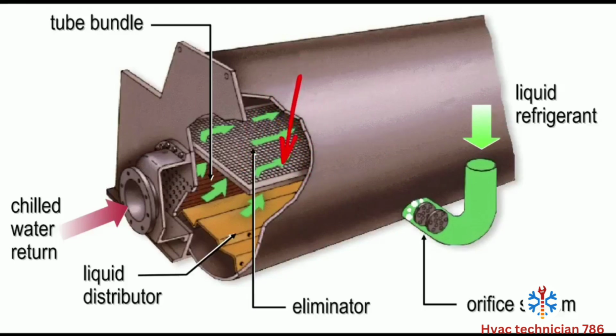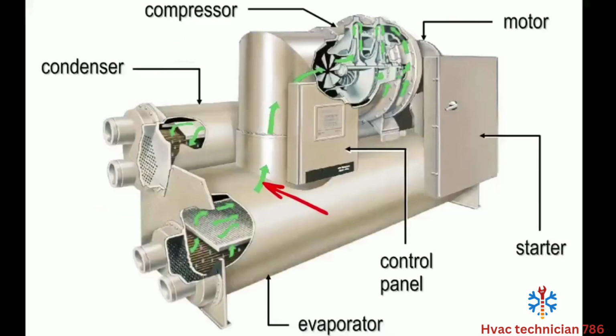So there is this eliminator. This eliminator does two things. Where our suction line is up here, it makes sure that that particular spot doesn't get more pulled than the rest of it, so that it literally doesn't raise up and start pulling refrigerant off the top of the evaporator back into our impeller, which is very bad. It's the same concept as flooding the compressor. So having this eliminator, it's really just a wire mesh screen at the top of the evaporator, forces the refrigerant to have a more even pull across the entire length of the evaporator, ensuring that we get full effectiveness of that evaporator as a heat exchanger. Because without that eliminator, this section right here would be favored because of its direct location to the suction line, and we would not get the full length of the evaporator fully pulling to the degree that we want to. But leaving the evaporator, we hit our suction inlet, we flow right back into the compressor, and the cycle starts over again.